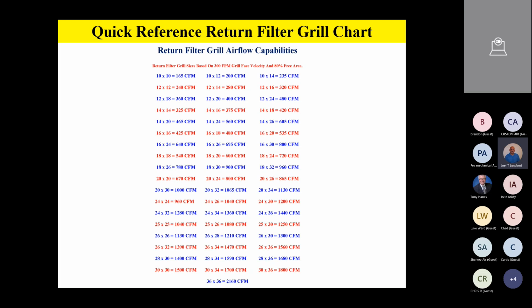And let me say that one more time. If you follow these recommendations on this quick reference, if you provide return air grills with filters in there, you will never get in trouble with undersized return grills. So that's just hard-learned experience here. That's 25 years of building duct systems and finding out that Manual D really does know what it's talking about. So good.